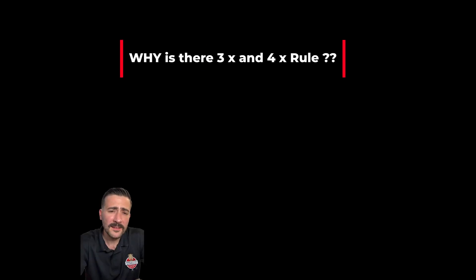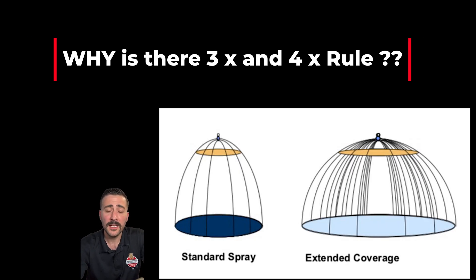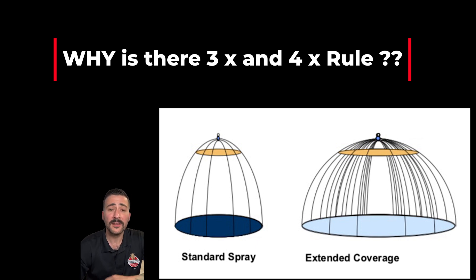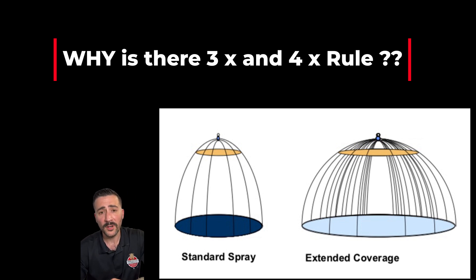So why is there a three and a four times rule? It's because of the difference in spray pattern. The extended coverage and the residential fire sprinkler have a much wider and higher spray pattern. The need for more space to develop that pattern is the reason why we go from three times with the standard spray to four times with the extended coverage and the residential — to give us more space to develop a spray pattern.